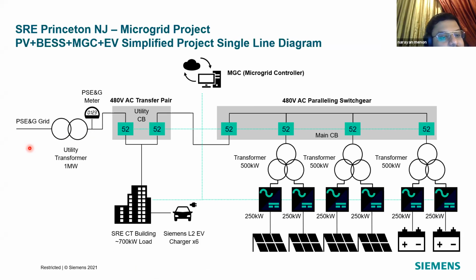Just an SLD on it, basically you had the grid, and most of the load was initially supplied directly from the grid. What we had done as an addition is put in solar arrays, approximately 1 megawatt peak, and a battery storage system, all connected via transformers, and then we connected them in parallel to the main utility transformer.